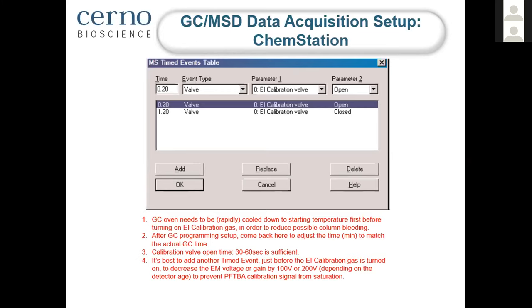We also recommend to add another timed event just before the calibration gas is turned on to reduce the electron multiplier voltage by about 100 or 200 volt, depending on the age of the detector. And this is to turn down the gain in order to prevent the calibration gas from saturating the detector. So those couple of notes, they're all described in a document, which I will show you later on in more detail with a lot of explanations. But that's the setup process for GCMSD under ChemStation.